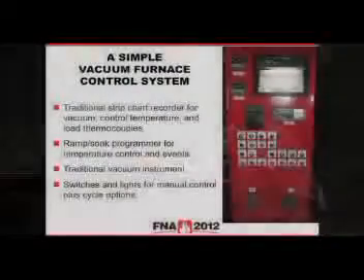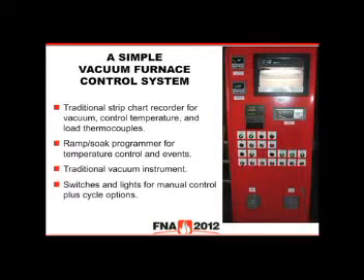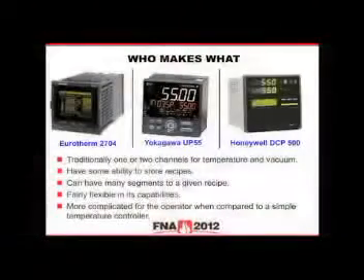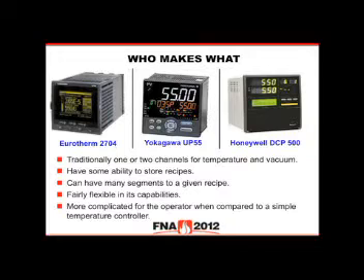Sometimes these might have one vacuum sensor, sometimes multiple. There's a high limit for protecting the furnace from runaway temperature conditions. This furnace had a flow controller for partial pressure flow control of hydrogen, which is unusual. Then a whole bunch of conventional lights and push buttons to operate the furnace manually or start the cycle, silence an alarm horn — switches to turn on the vacuum pump, do a manual backfill or cooling. Inside, probably some relays. There's no program to forget, simplified troubleshooting — it's got a lot going for it.